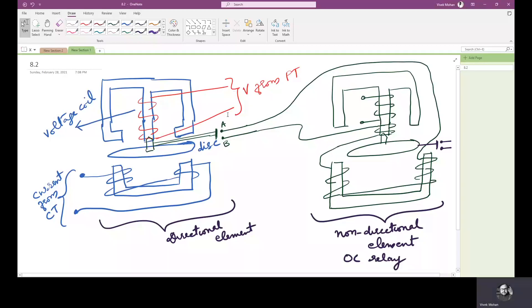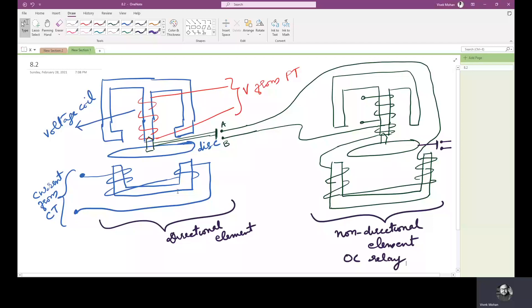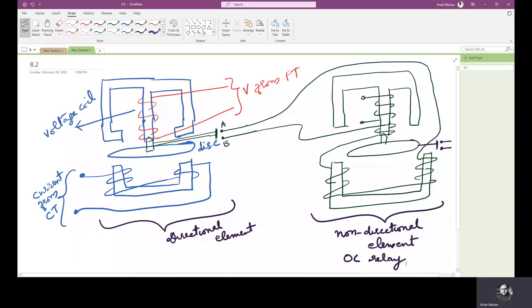The directional element has two parts: a voltage coil and a current coil — two magnets wound with voltage coil and current coil respectively. The voltage coil of the directional element is energized by the system voltage through a potential transformer or VT, that is, a voltage from the potential transformer or voltage transformer.